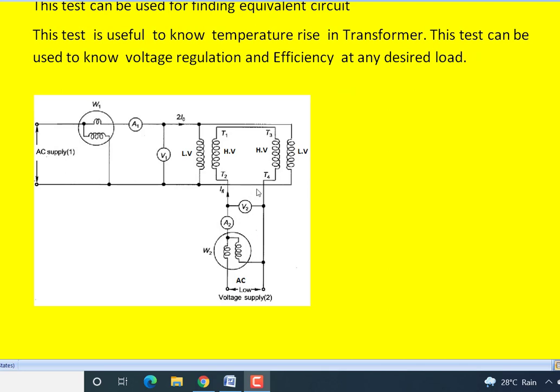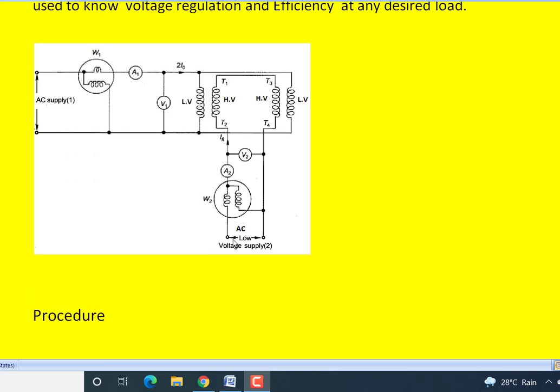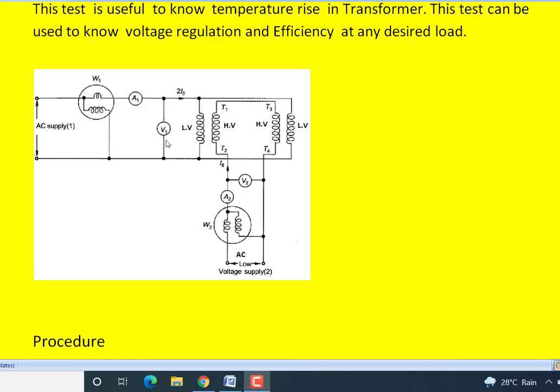Once we know all these readings, we can calculate the individual transformer no load current, the applied voltage to the primary, and the core loss of each transformer. Similarly, we can calculate the copper loss of each transformer at full load condition. This ammeter shows the full load rated current of the secondary of the transformer, and this V2 represents the applied voltage under short circuit conditions. Short circuit conditions means the voltage induced in this and the voltage induced in this are equal and opposite, so the net voltage across this will be 0, whereas the applied voltage from the supply will be read by this voltmeter.